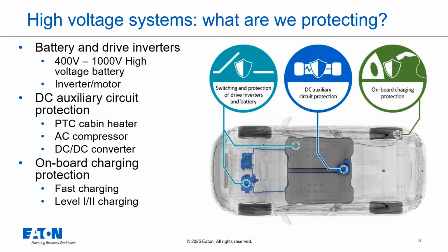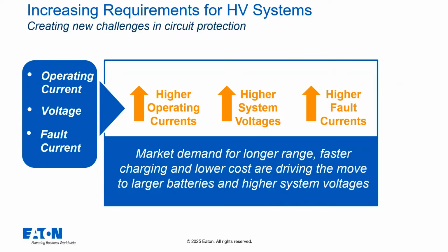The EV market is constantly evolving, and that's creating new challenges for circuit protection. What's driving this? Customers want longer driving range, faster charging, and lower costs. To meet these demands, manufacturers are using larger batteries and pushing for higher system voltages. Electrifying larger vehicles also requires higher power levels. All of this directly impacts the demands on our circuit protection, specifically leading to requirements for handling higher operating currents, higher voltage systems, and crucially, higher fault currents. We'll look at each of these impacts in a bit more detail.